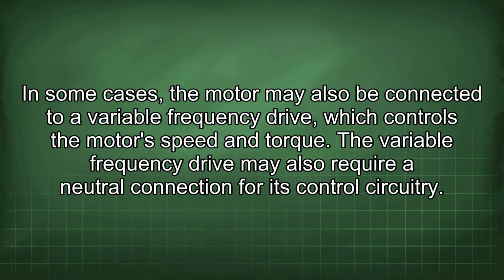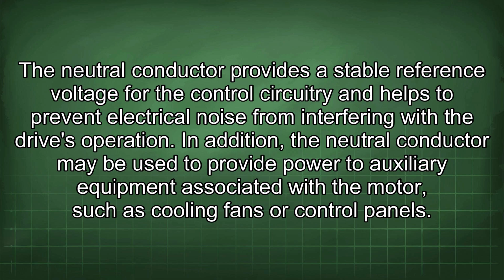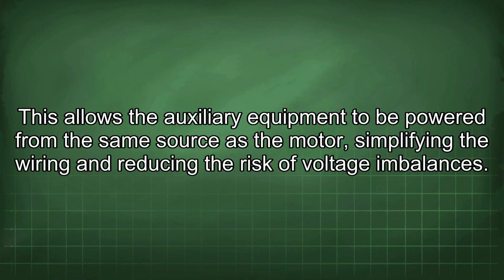In some cases, the motor may also be connected to a variable frequency drive, which controls the motor's speed and torque. The variable frequency drive may also require a neutral connection for its control circuitry. The neutral conductor provides a stable reference voltage for the control circuitry and helps to prevent electrical noise from interfering with the drive's operation. In addition, the neutral conductor may be used to provide power to auxiliary equipment associated with the motor, such as cooling fans or control panels. This allows the auxiliary equipment to be powered from the same source as the motor, simplifying the wiring and reducing the risk of voltage imbalances.